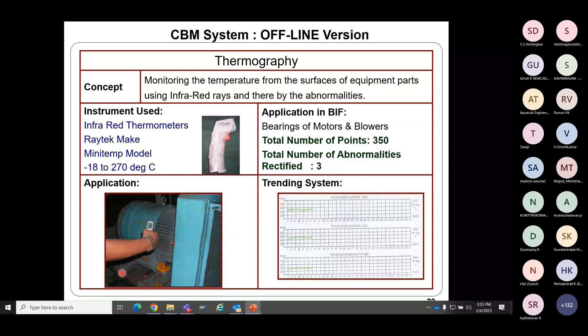So you may decide at what level the acceptable range of temperature is okay, based on which you can arrive at many points equipment-wise, and then you can start practicing such things. This comes under thermography. Again, you are using thermal analysis with IR radiance from the surface of the part, where you are able to find abnormalities. This is specifically used in high voltage systems, even in HT, where any loose connections and the like can be seen even when the system is live.